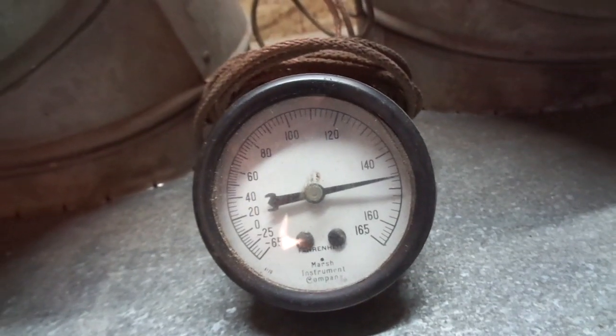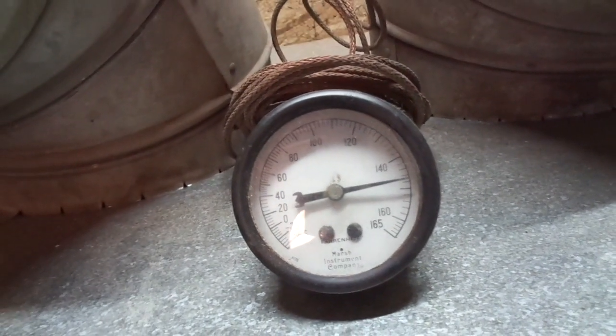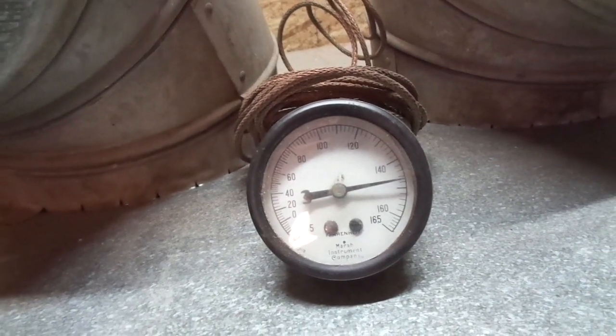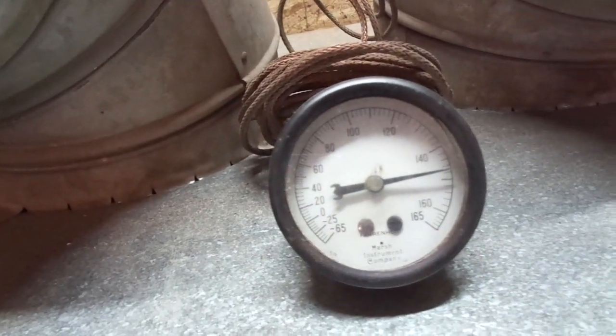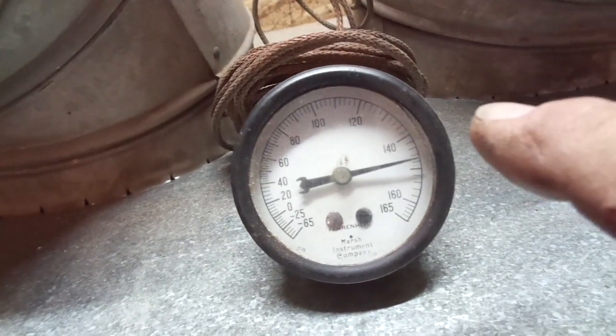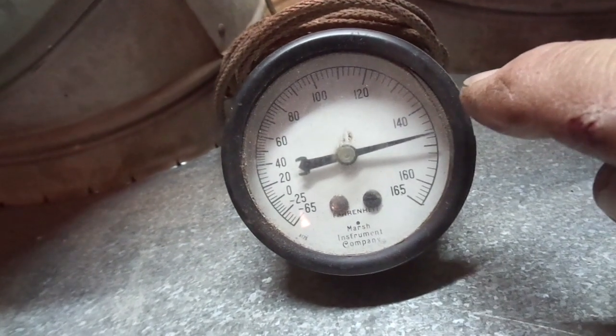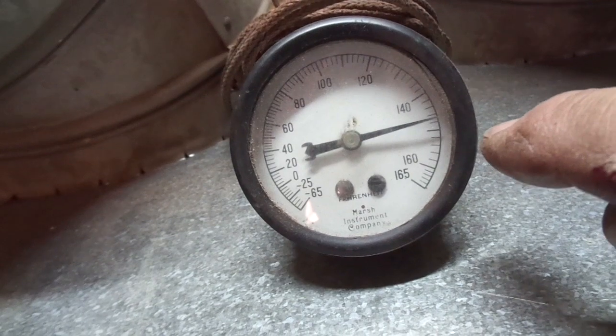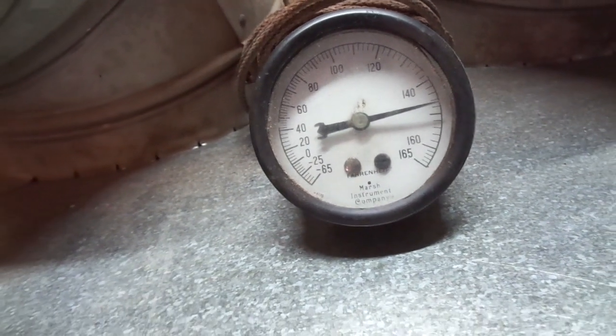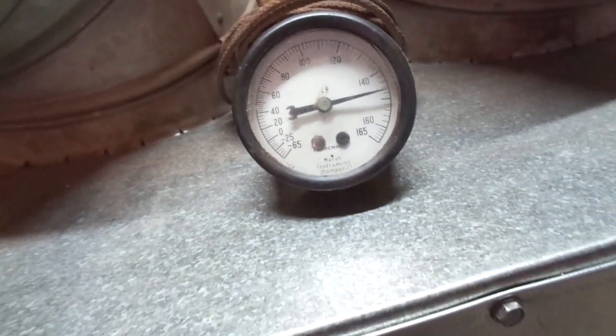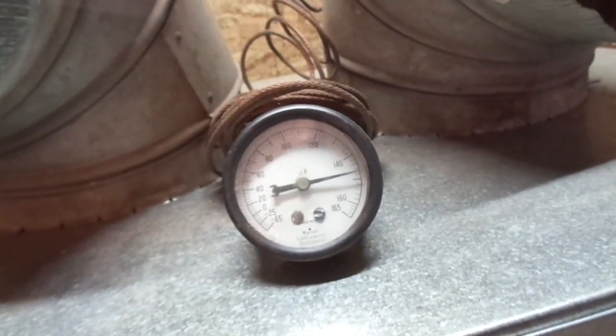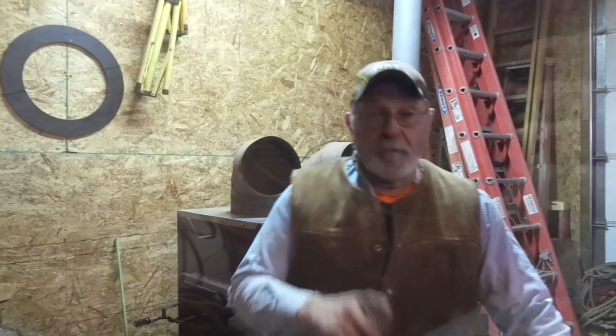Normal fossil fuel furnaces, like natural gas furnaces, propane fired furnaces, and oil fired furnaces, operate off of roughly a 70-degree temperature rise. If you take a look right here, you can see 140, 150, so about 146, 148 degree discharge temperature coming right off of this. When I talk about temperature rise, it is the amount that the air rises to as it comes in the return and passes across the heat exchanger of your furnace and comes out the top.